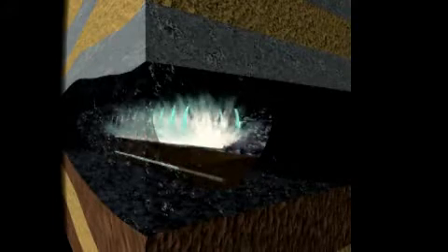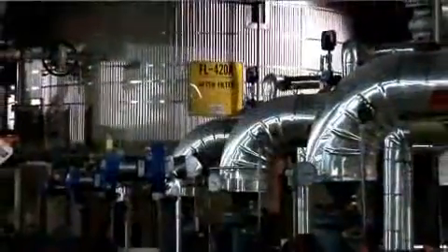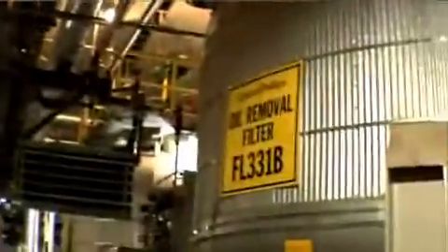The steam condenses and turns into hot water. The resulting oil and hot water mixture is piped from the producer well back to the plant to be separated and treated. It is first de-oiled and then softened by removing the magnesium and calcium hardness.